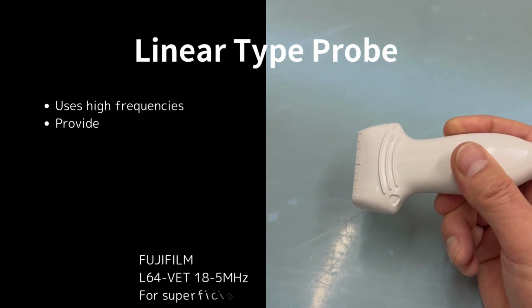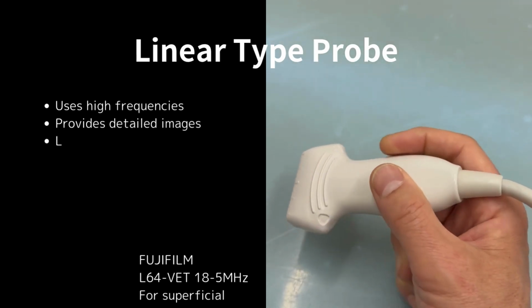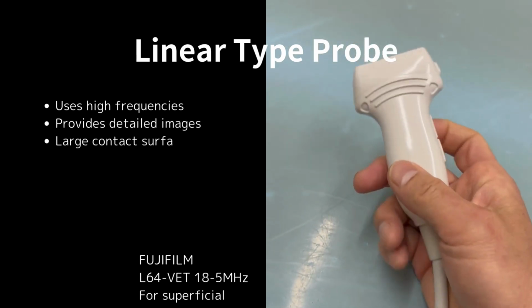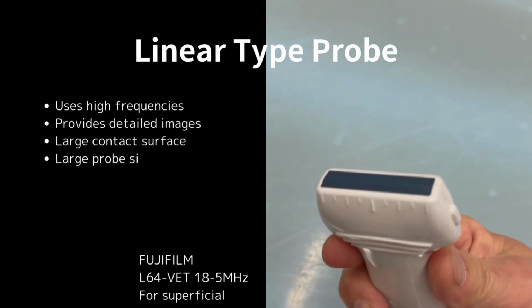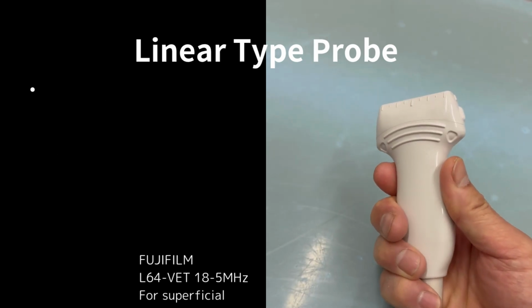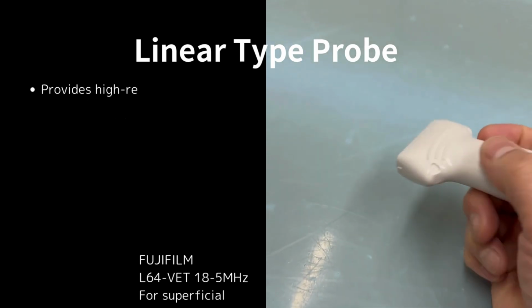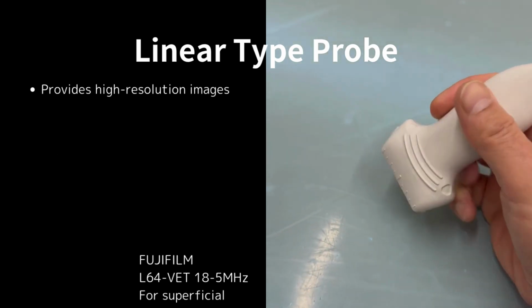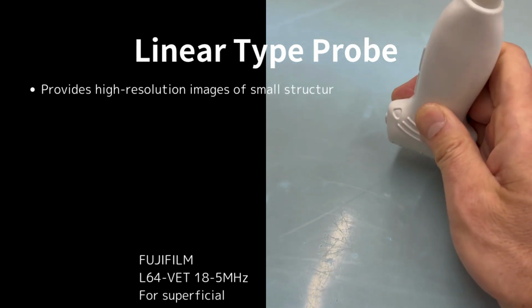Next, let's go over the linear probe. The image quality is excellent with this type. Because it can operate at high frequencies, it gives you very detailed views of small structures. However, the large footprint can make it more sensitive to hair artifacts, and the size of the probe itself can make handling a bit more difficult.